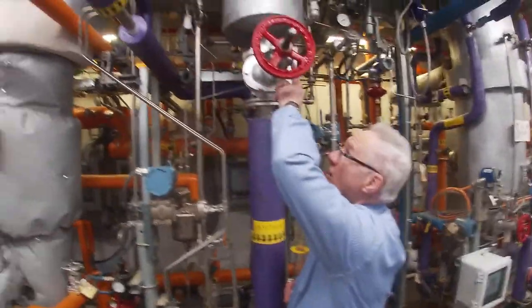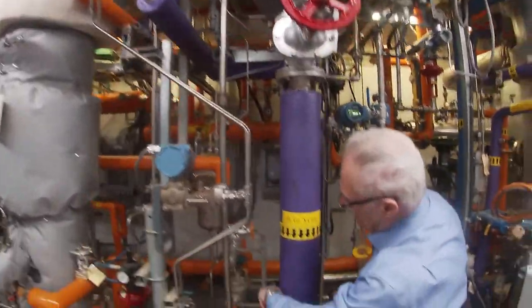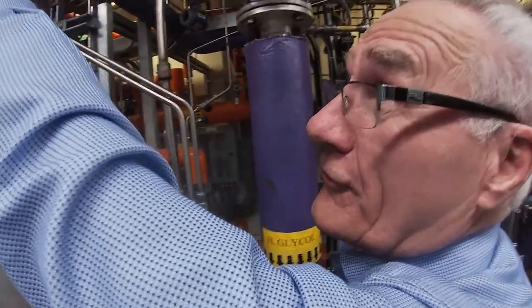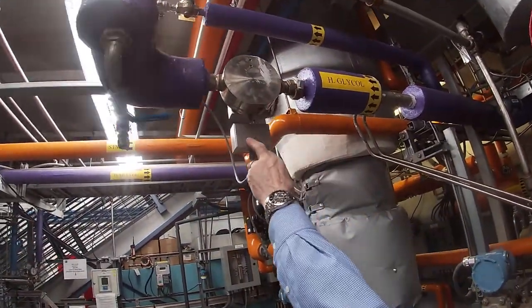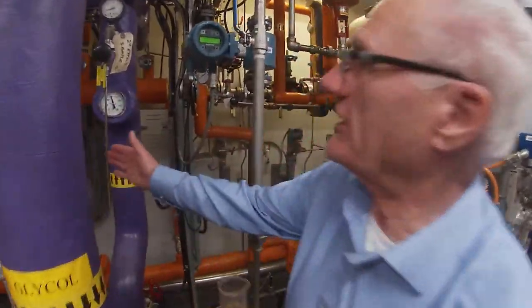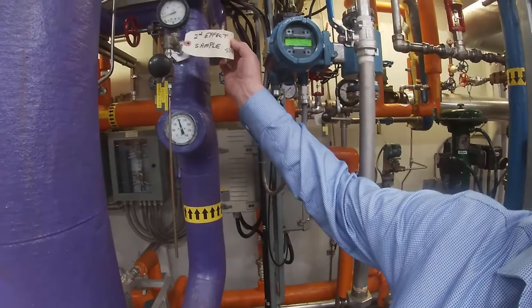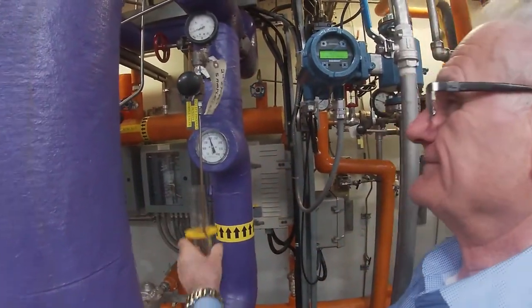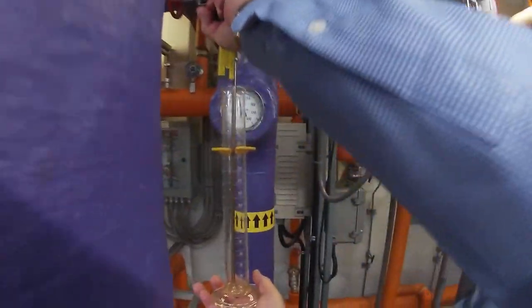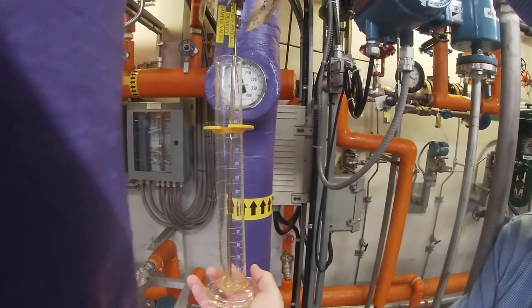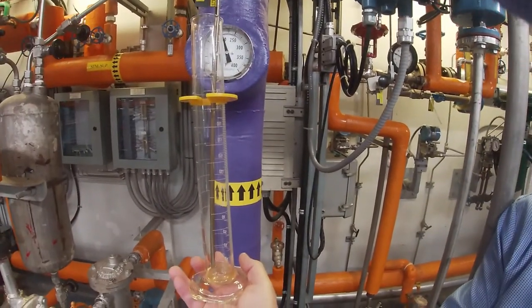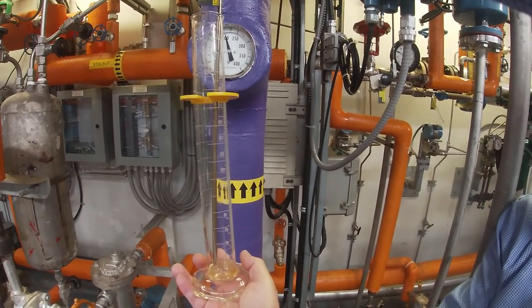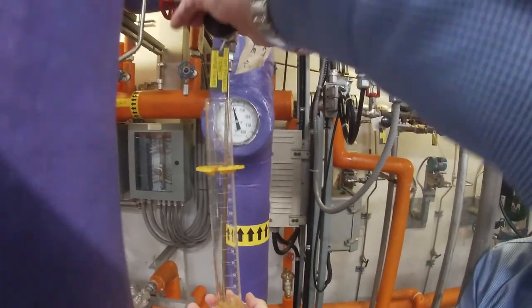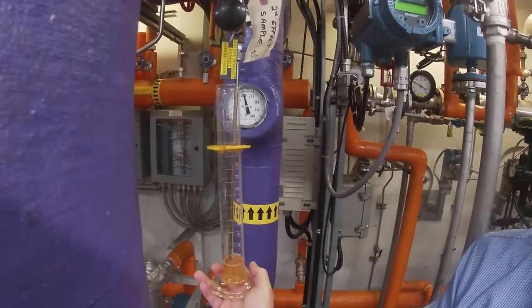So the glycol from the second effect evaporator is circulating around through this line and back up to the solid film heat exchanger. There is our refractometer. So it's on that recirculation line. So we're going to take a sample, second effect sample, from this point. And this one doesn't matter how fast you take it, because it's just off that recirculating glycol. You have to open the valve quite a bit because this vessel is running under vacuum.